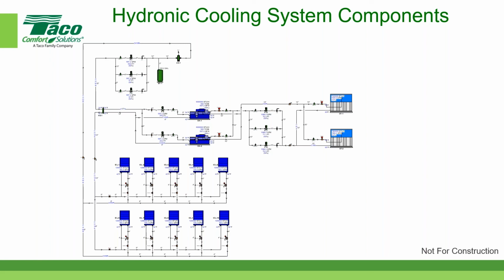But if you actually work with a chiller manufacturer for a specific set of conditions, you may find that it doesn't require 3 GPM per ton. It can't run less than 2.4 GPM per ton, or else the heat rejection or the inefficiency of the chiller wouldn't exist, and you can't have that. You can't have a chiller that's 100% efficient. So it's obviously going to be greater than 2.4, so it's probably going to be somewhere between 2.6 and 3 GPM per ton. And again, you get that information from the chiller manufacturer based on a specific set of operating characteristics.